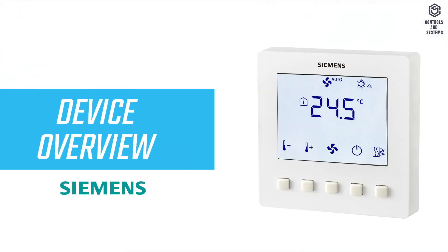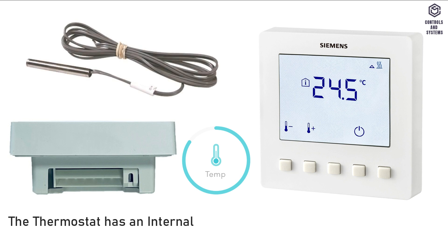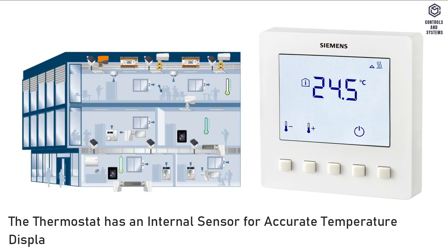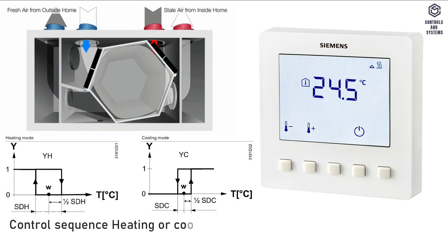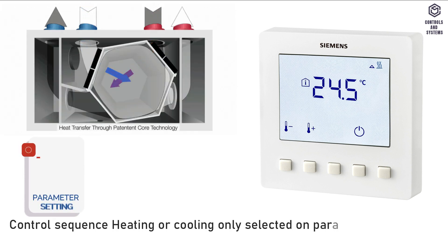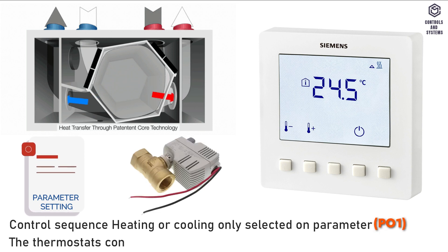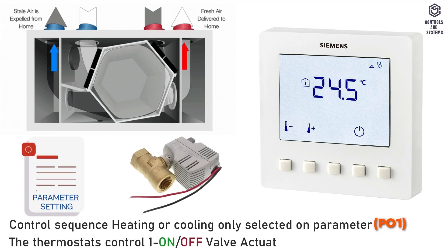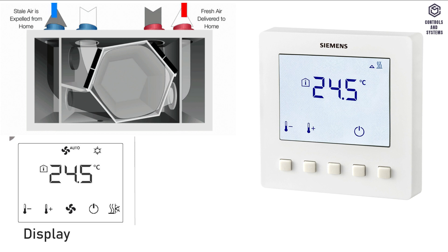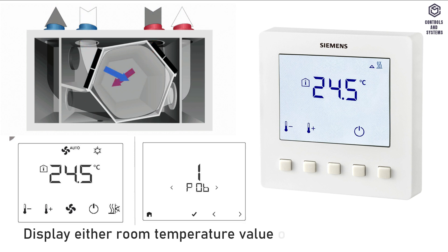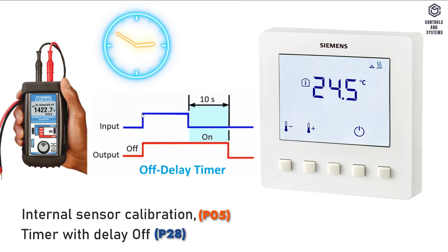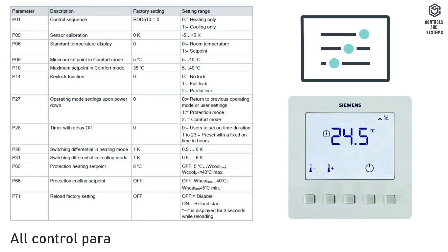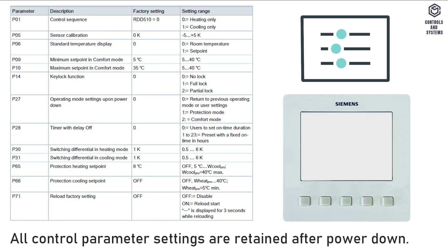Device overview: the thermostat has an internal sensor for accurate temperature display and to maintain room temperature. Control sequence — heating or cooling only — is selected on parameter setting. The thermostat controls one on/off valve actuator. The display shows either room temperature value or set point value, selected on parameter setting. Internal sensor calibration and timer with delay-off controls are available, and all control parameter settings are retained after power down.